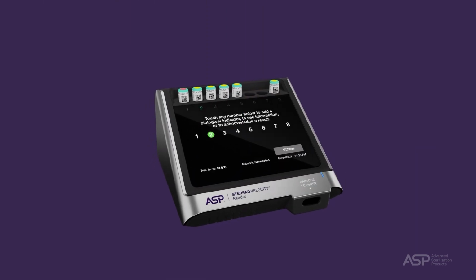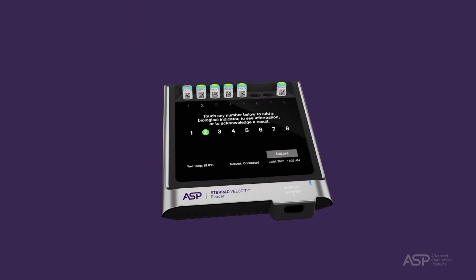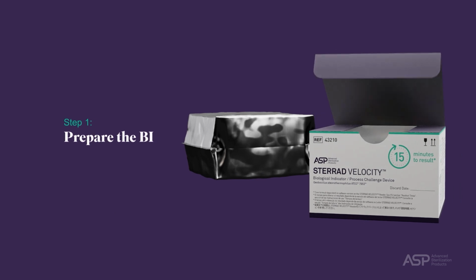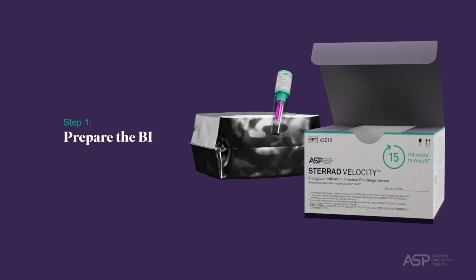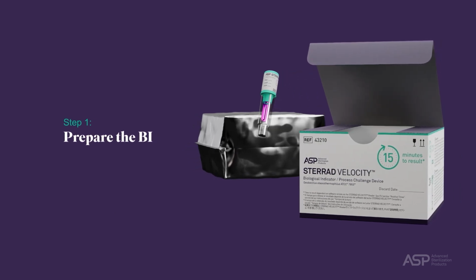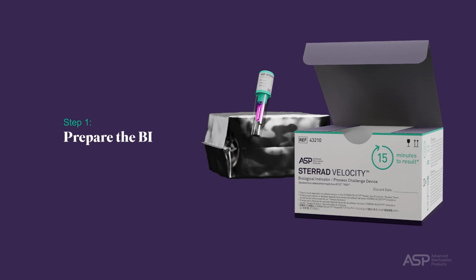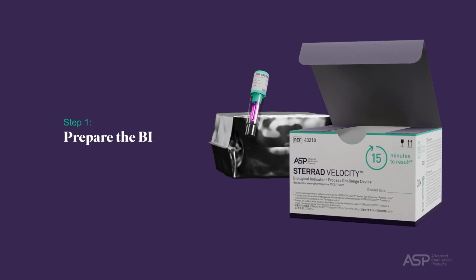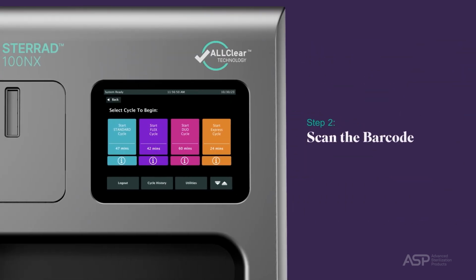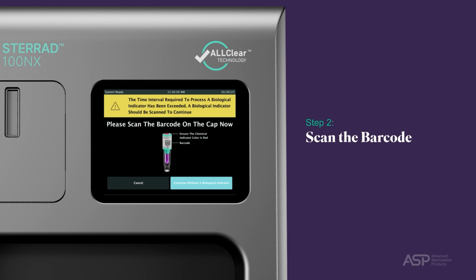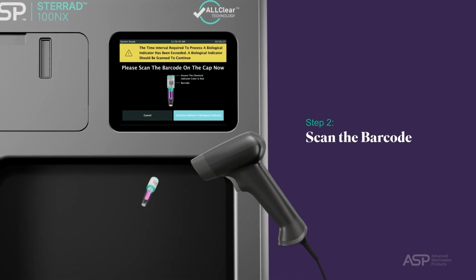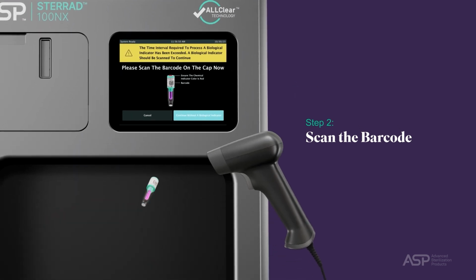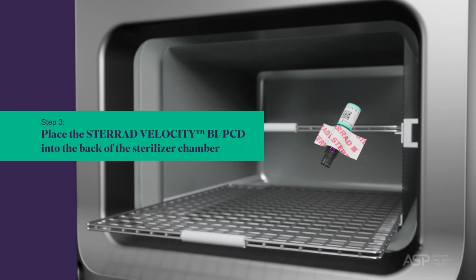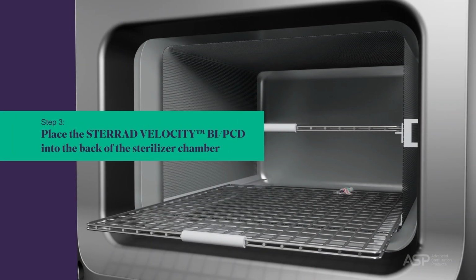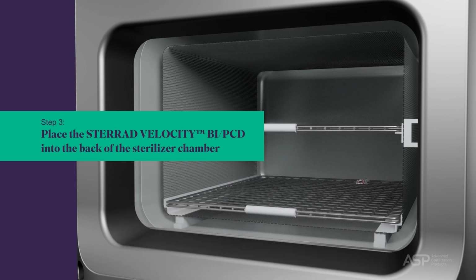When using the STERRAD Velocity system, the following steps should be followed. Step 1. Prepare the STERRAD Velocity Biological Indicator (BI)/Process Challenge Device (PCD) as specified in the instructions for use. Step 2. After selecting the desired cycle, follow the on-screen instructions to scan the barcode with the sterilizer scanner. Step 3. Place the STERRAD Velocity BI/PCD as specified in the instructions for use.